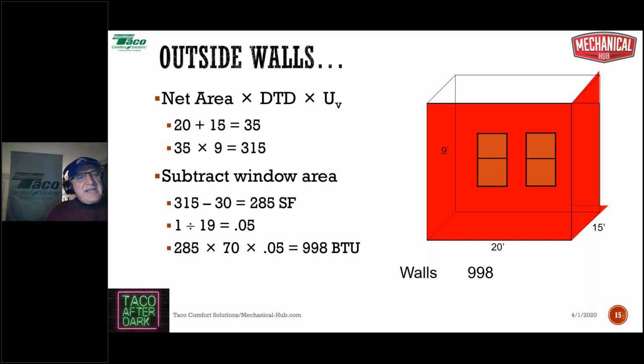For this example, let's say it's R19, 6 inches of fiberglass. I know there's other stuff here, we'll round up to get it, but let's take a look at the biggest structure there, and that's the fiberglass. 1 divided by 19, which is the R value, 1 divided by R equals U. So in this case, 1 divided by 19 equals 0.05. We'll round up, call that good. This is a nice little piece of fudge if you're looking for some right here, okay? I know there's studs, I know there's other stuff involved. Again, not flying it to the moon, just trying to heat it up, okay?